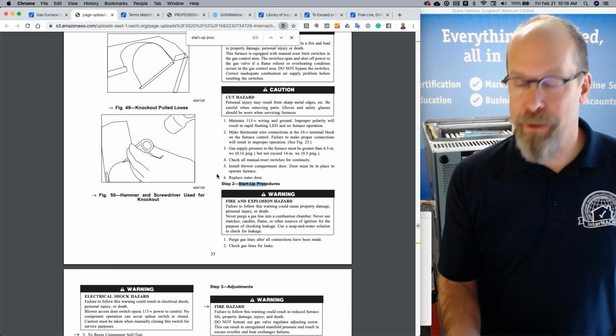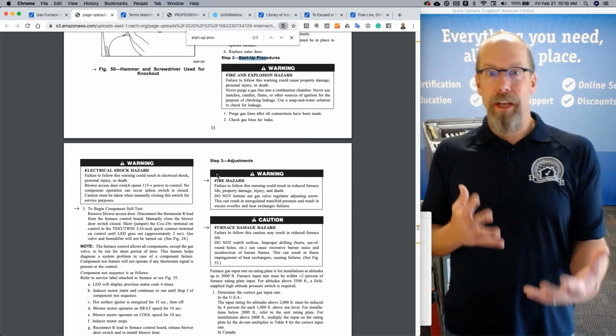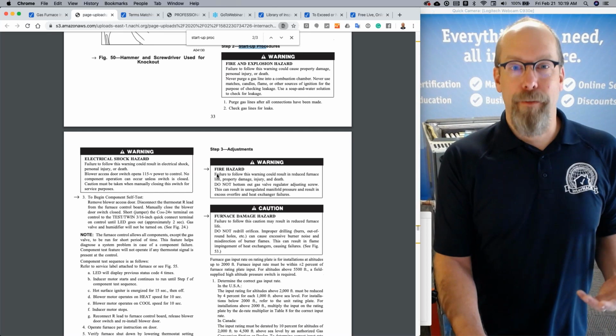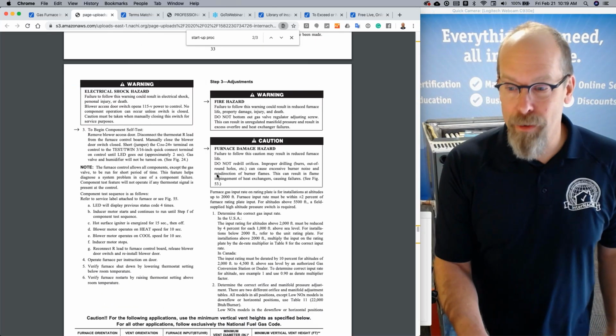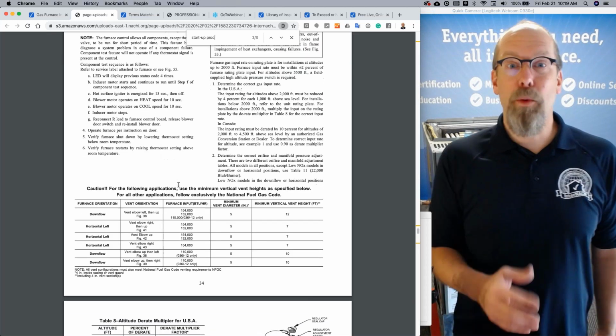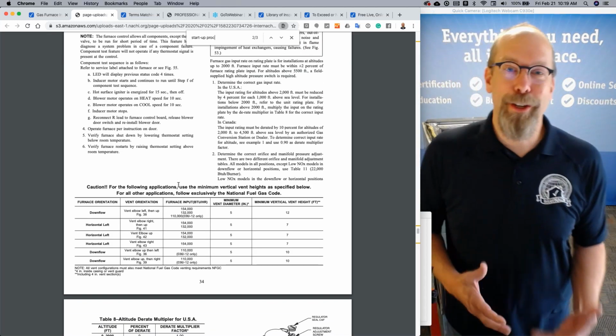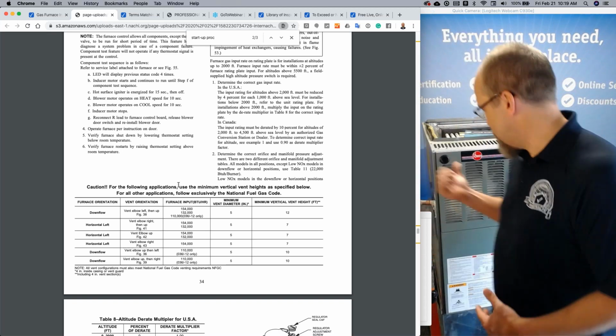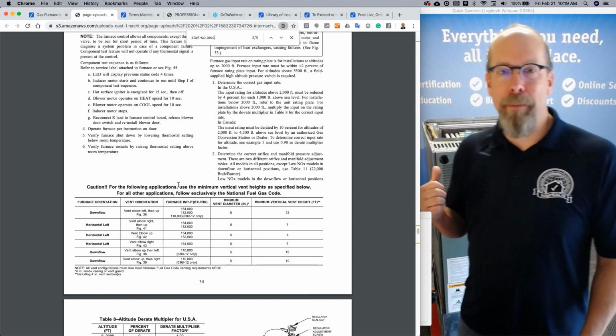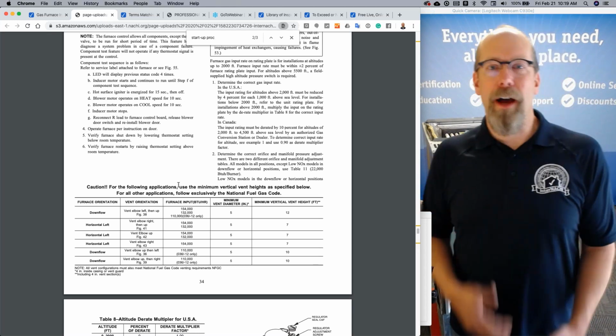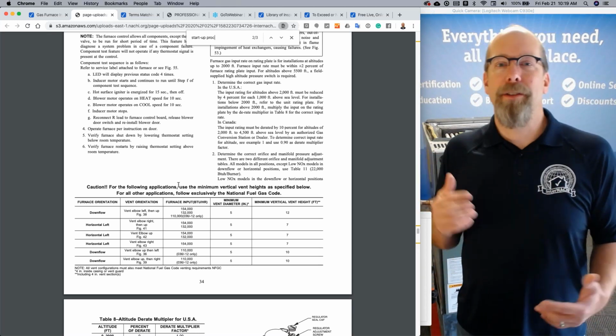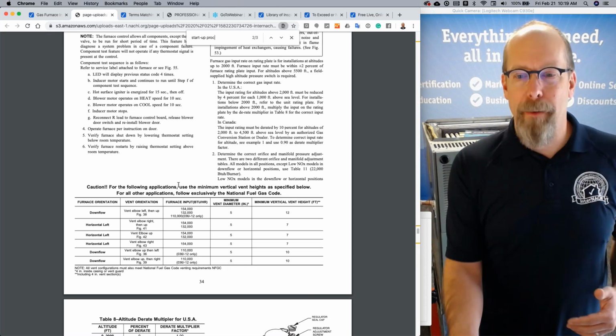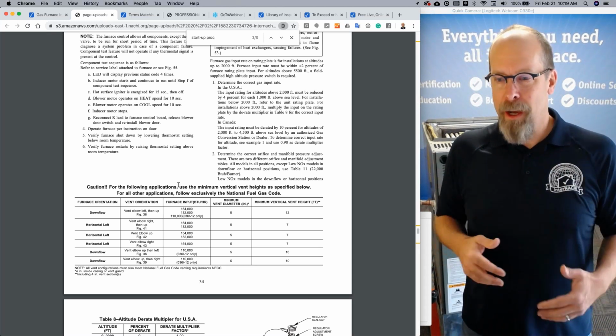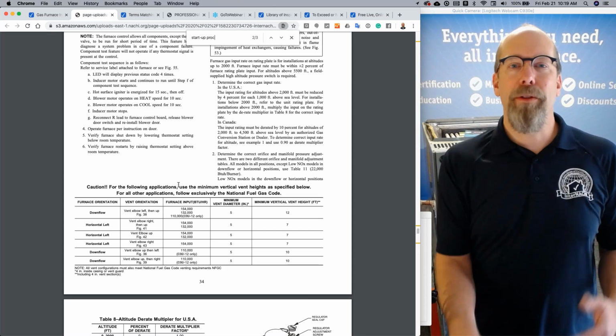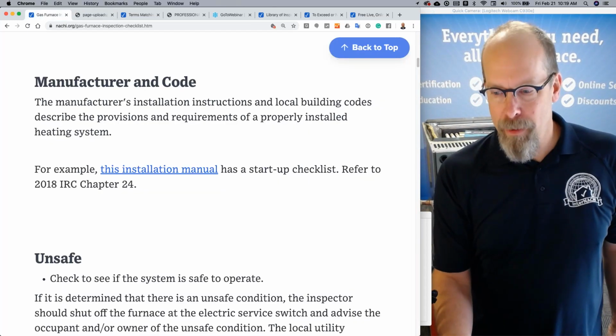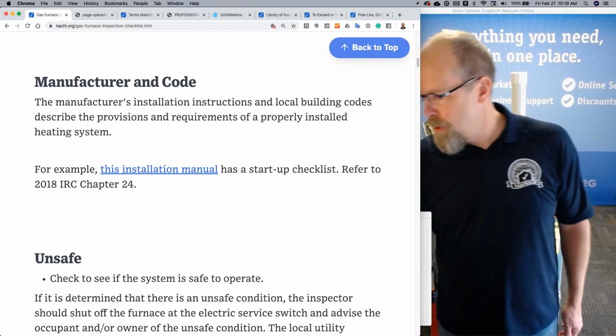There's a startup procedure, and this is written for the technician installing the system and starting it up for the first time or two or three, just to test the system. You can go through the startup process and see what an HVAC technician is required to do, their standard, to make sure that the heating system, like the Rheem heating system behind me, starts up properly. What is the step-by-step process? And we used the manufacturing recommendations of several manufacturers and also code to help build this checklist that we're going over right now.